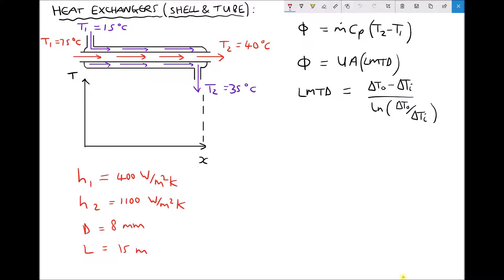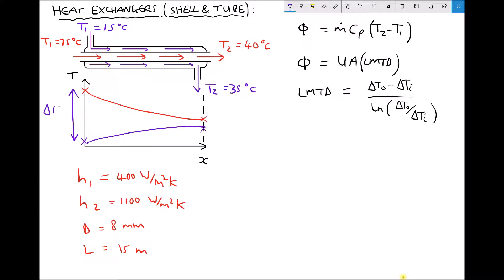On the left hand side the hot fluid starts at 75 degrees C and drops to 40 degrees C. The cold fluid starts at 15 degrees C and rises to 35 degrees C. Delta T_I and delta T_O for the log mean temperature difference can be taken from this diagram: delta T_I is the difference between the two inlet temperatures on the left, and delta T_O is the difference between the two outlet temperatures. We'll calculate delta T_I, delta T_O, then U and A, and finally the rate of heat transfer.